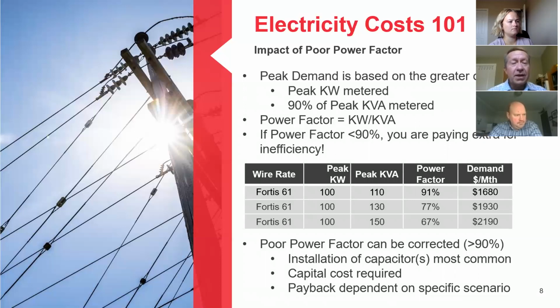So you can see in that first example, the power factor is 91%, so it's above 90, so you're actually billing on the peak kilowatts. But in the next two examples, where it drops to 77 and 67%, you're being billed on the peak kVA because that starts to rule.